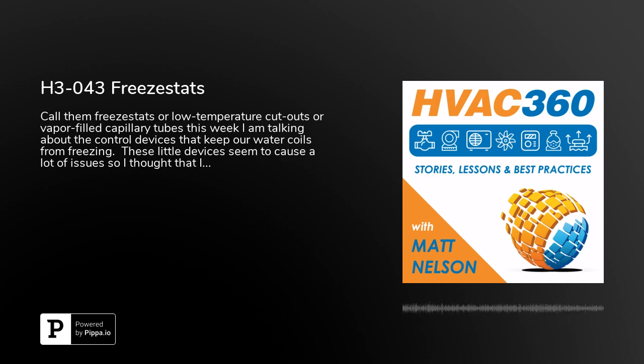Now, most of those probably aren't going to see a lick of duty, but you really need to have that coil coverage just in case. So, like I said, you could end up with 5 if you have something that's 50,000 CFM. Of course, that's not to say that if you had 11,000 CFM, one sensing element wouldn't necessarily cover the entire coil, but it's just something that you need to be aware of. Typically, as a commissioning agent, if I see a poorly covered coil, I'm going to request that additional sensing elements be placed on the coil to get that proper coverage.